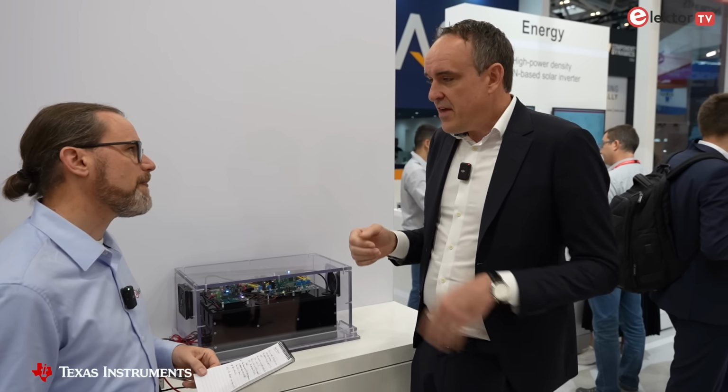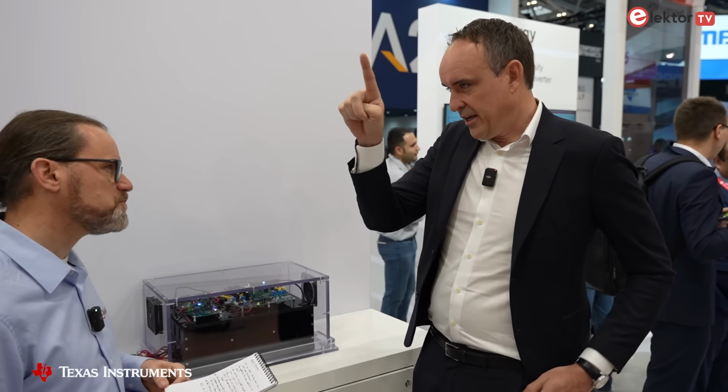Yep. Number one. Number two is that the arcs are also in a DC fashion, which means that any traditional method to detect arcs is more complicated, because in AC arc detectors, very often referred to as AFCI, arc fault circuit interrupters, you always have a periodically changing wave. So you have a 50 hertz or a 60 hertz wave. It also means that the arcs are going to come periodically. Yep.